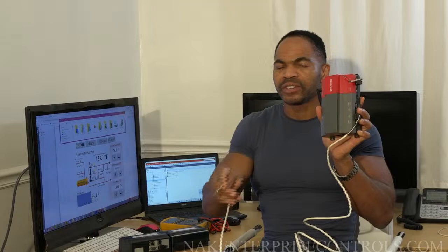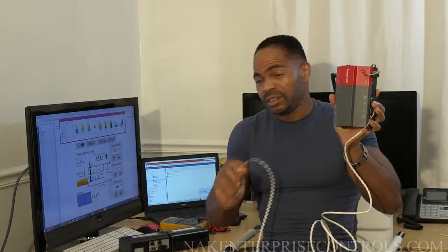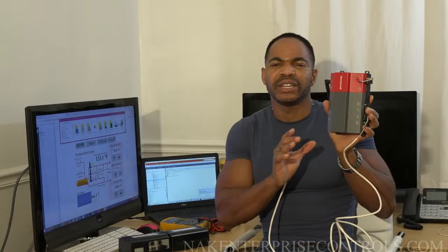For example, you have your Jace on the first floor, and you have an AHU on the second floor. You can run an MSTP to the second floor, and put the IO there for that AHU. So in this case, it's great. You don't have to put everything in the panel like the AX. So that's one of the benefits.